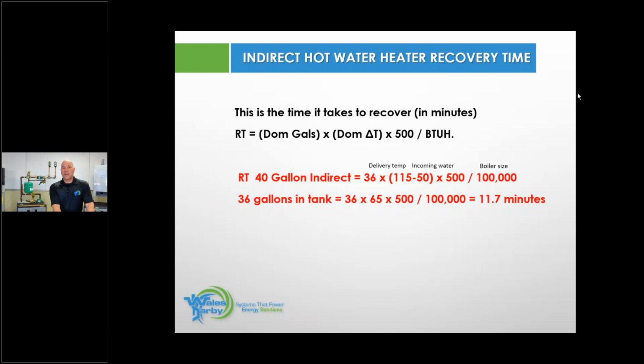We're going to stick with the same size tank. I want to deliver 120-degree water to my sink, so that 115 will be replaced with 120. Still going to leave 50-degree water incoming. Could be 40, we're here in the Northeast, but most common, we'll call it 50. Going to leave the 500 the same, but you're going to take your boiler size, and you'll understand the method to my madness in a little bit, and make that 40,000 BTU.